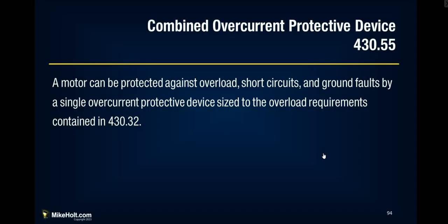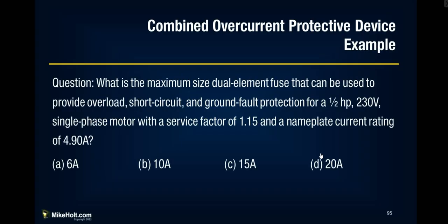We are continually installing stuff that is protecting against ground faults, arc faults, short circuits, overloads, overvoltages, surge protection. And that's what we are installing equipment to keep that from happening. As they say, the lightning that we're putting in these systems, all this stuff that we're installing in these buildings, this is the stuff that protects it from getting out of control. A motor can be protected against overload, short circuit, and ground faults by a single overcurrent protective device sized to the overload requirements. That's also true.